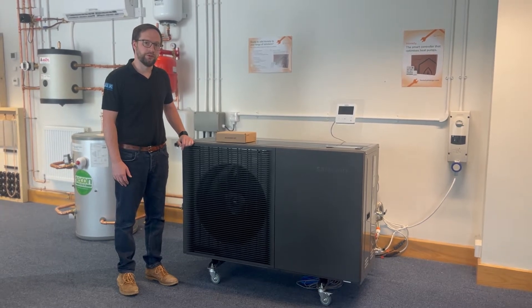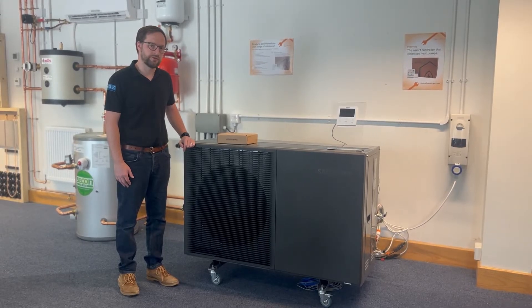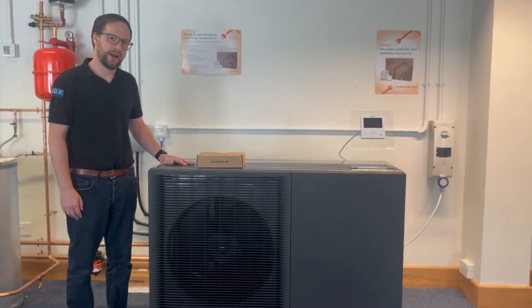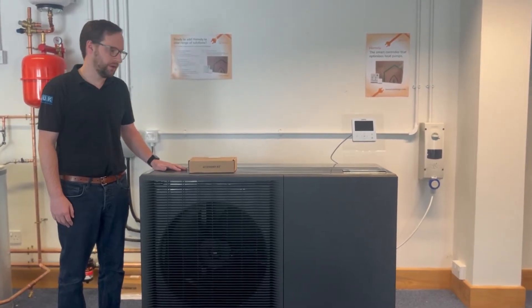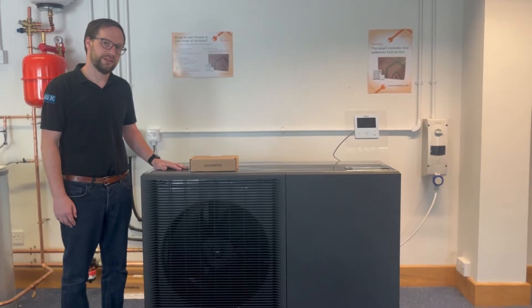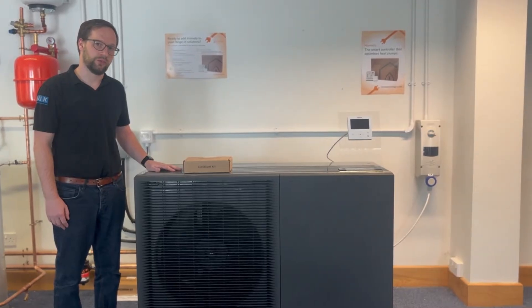My name is Nick Eastwood from Seacon Renewables, and I would like to introduce you to the new Samsung Gen 7 Integrated Hydro unit. This unit is Samsung's new R290 unit, with a low GWP refrigerant of only three. This unit is capable of doing 75 degrees in heating down to minus 10, and 65 degrees down to minus 25.